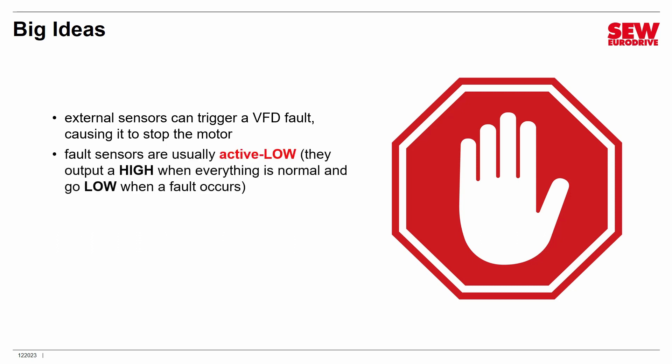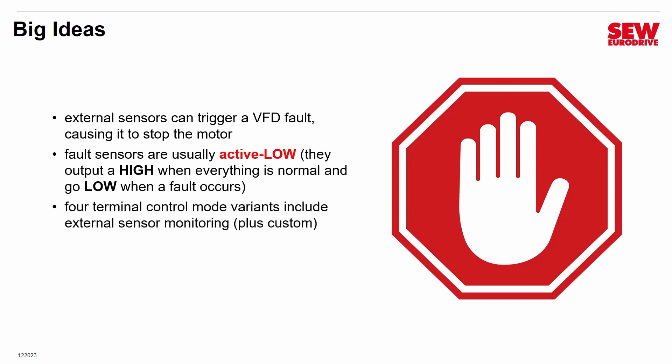Fault sensors are usually active low — they behave like a normally closed switch. When everything is normal they're outputting a high signal; they go low when the fault occurs, like a normally closed switch that opens. The MOVITRAC LTE-B supports four different terminal control variants that can monitor an external sensor, plus a totally custom one, so really five — but we'll be looking at the four predefined ones.